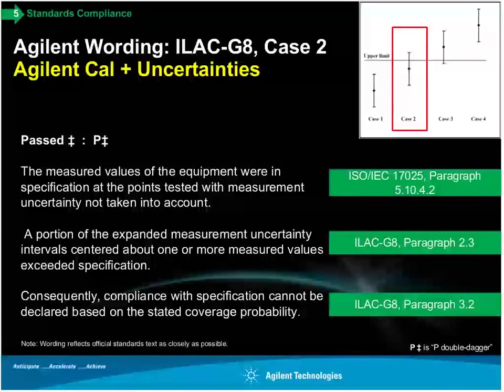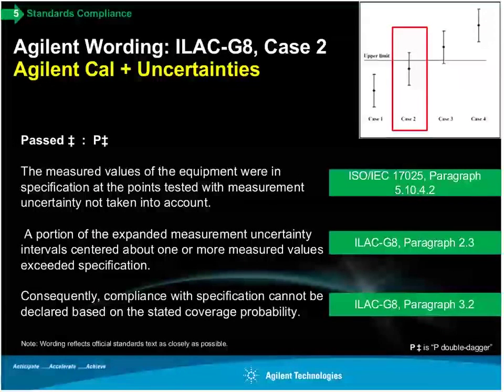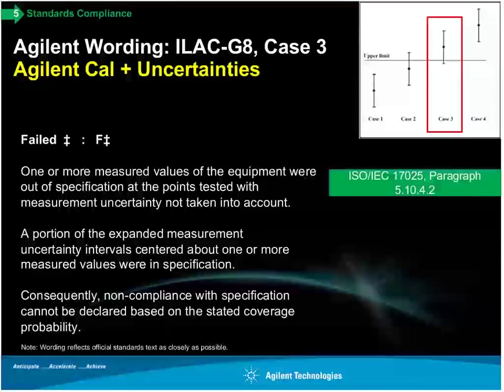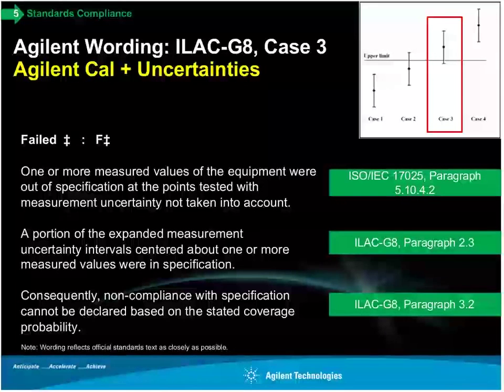Keep going. Okay. On this slide, we show that Agilent is moving towards complying with the ILAC G8. Now, in the United States, there is some difficulty with G8, and the modifications being made to it at the moment will handle that to some extent. But I would applaud a situation in which a very clear pass-fail statement, with mention of the uncertainties and how they're taken into account, should appear on the certificates, in my view. And I understand that the Agilent Cal Plus Uncertainties service is going to do that. Other laboratories in Europe do this, increasingly so, and I'd like to think it will increasingly spread across the United States.